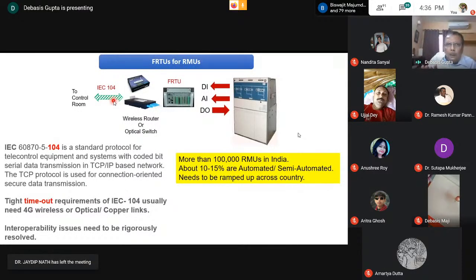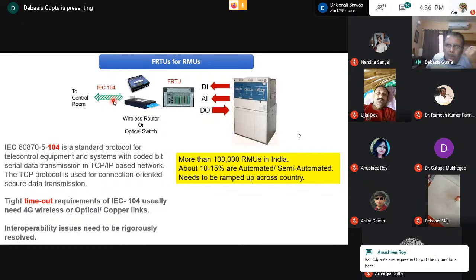IEC 104 is good and bad. Why is it good? It assures you absolutely deterministic times by which you can get an operation done. If a breaker trips here and it's reported after 5 seconds, heavens won't fall. No problem. If there is a load showing 100 ampere and I come to know after 10 seconds also, heavens won't fall. But if I switch off something and tell a person you can work on the line, and then it switches off late, then heavens will fall.